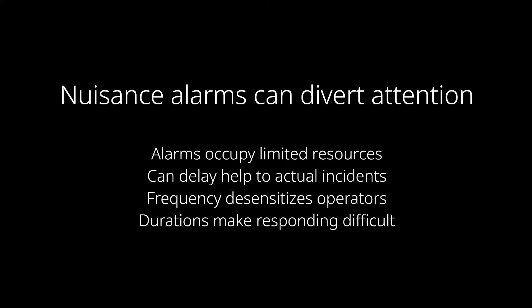Shelving can be used for nuisance alarms, such as alarms that trigger excessively even after the operator acts. Nuisance alarms can divert the attention of a control room operator unnecessarily. These alarms may transition states often and can be classified as chattering or fleeting alarms. They're often short in duration where the operator can't act. These types of alarms can be due to design issues, faulty instrumentation, or a process unit being out of service.